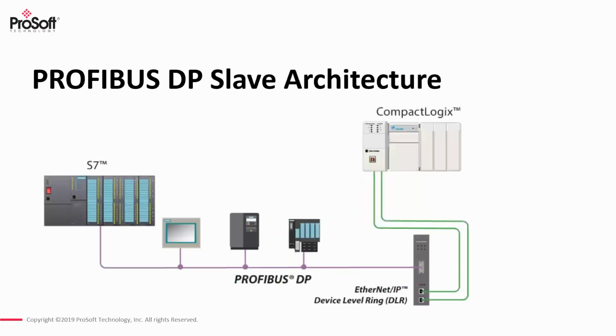When we talk about a PROFIBUS DP slave, the typical applications we see are where we need to participate as a PROFIBUS slave device on the network. For instance, if you needed to pass data from a CompactLogix processor out to something like a Siemens Step 7 processor, there may be things like an HMI, drive, and distributed I/O out on that network, and you need to pass that information over to the Siemens Step 7 processor from a CompactLogix controller.